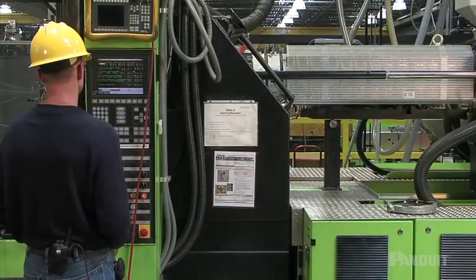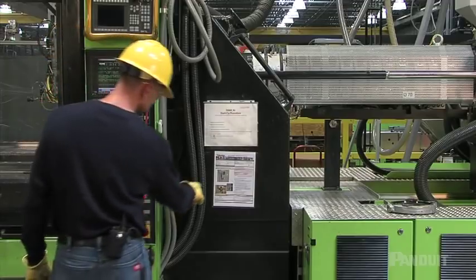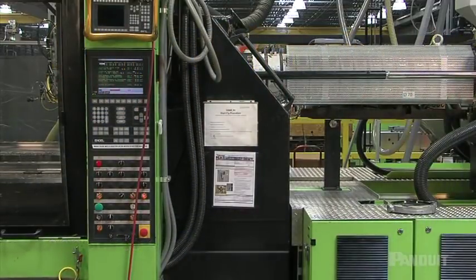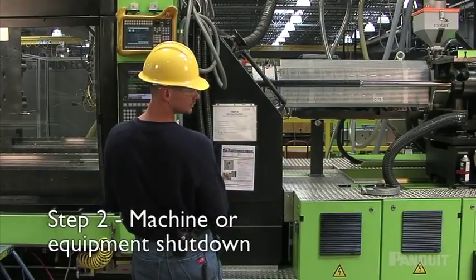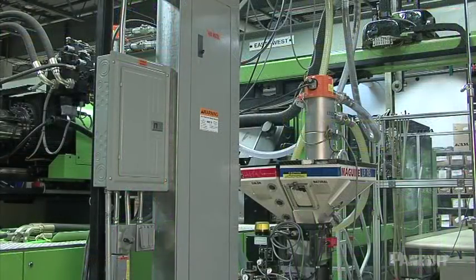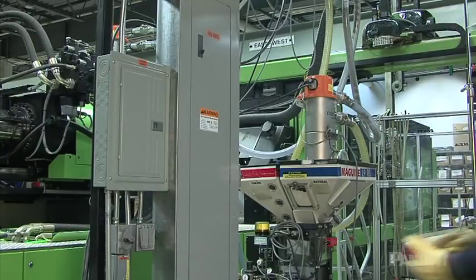Now let's take a look at some example lockout-tagout practices. The procedures for shutdown and startup should be straightforward. When equipment must be shut down for maintenance or repair, make sure you understand the type and magnitude of the energy, the hazards to be controlled, and the methods to control the energy before attempting to shut it down. After preparing for the shutdown and announcing it to all affected employees, turn off the equipment using normal stopping procedures. Then disconnect the power source or sources to isolate the equipment. In the case of electrically powered machines, this means taking action at the disconnect or breaker that feeds the machine.